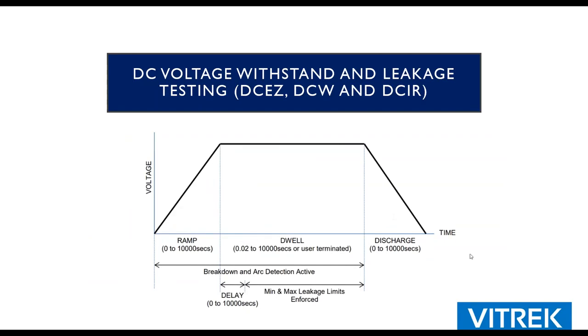All right, so you have this test. It's broken up into multiple parts. Typically, you're going to have a ramp that you can define based on time, or in some cases current, if you wanted to charge at a specific current. Then you have the dwell time. Dwell time is how long you're going to hold your device at that test voltage. And then obviously discharge, which is either going to be fast, which is the normal setting, or you can have a ramped discharge if you choose.